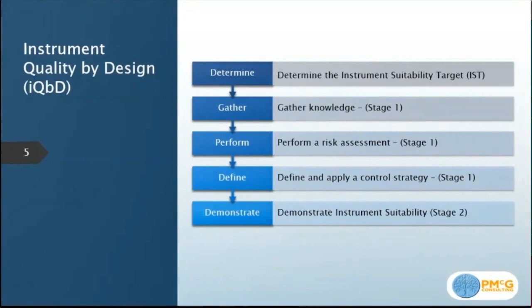This is an example of what an IST could look like. Instrument performance is generally measured in terms of peak response, so peak shape, resolution, retention time, sensitivity. As you can see, some of these key factors are captured with acceptance criteria in our example of the IST.